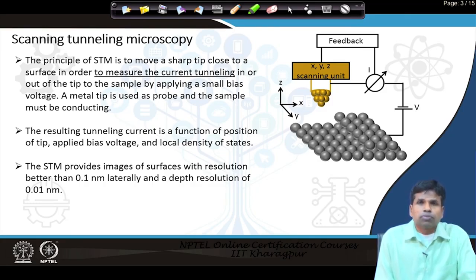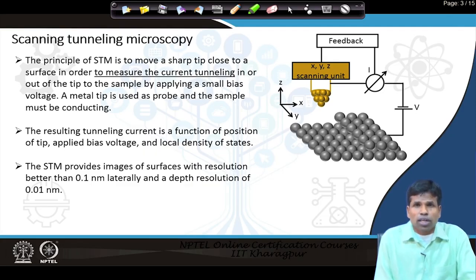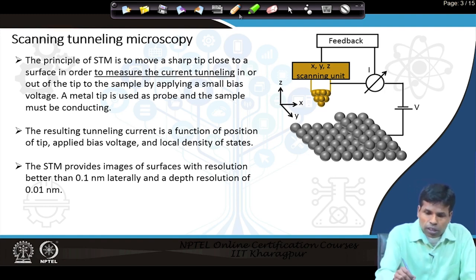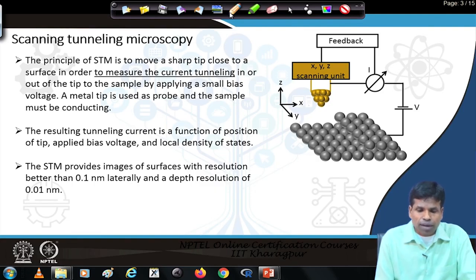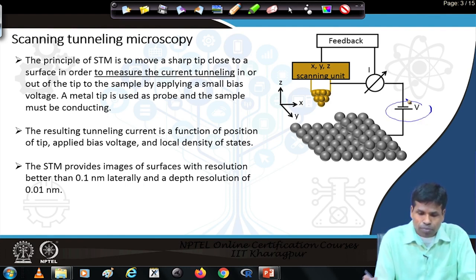Tunneling stands for measuring the tunneling current. Tunneling current is the current that flows from the sample to the tip, or tip to the sample, via a tunneling mechanism. The principle of STM is to move the sharp tip close to the surface in order to measure the tunneling current. Tunneling current can flow into or out of the sample, and that is done by applying a bias voltage.